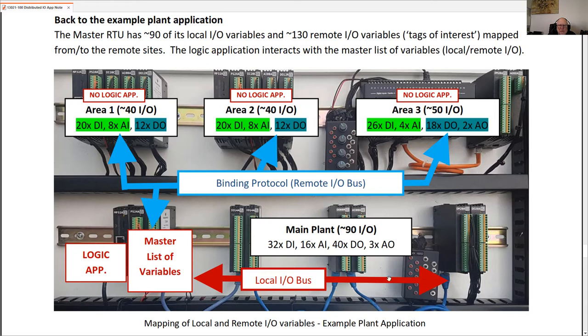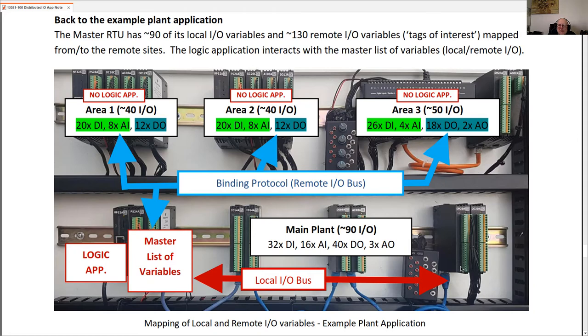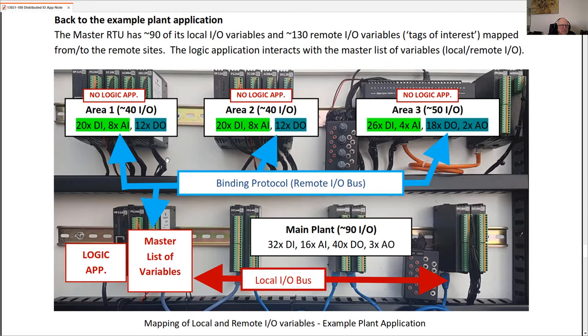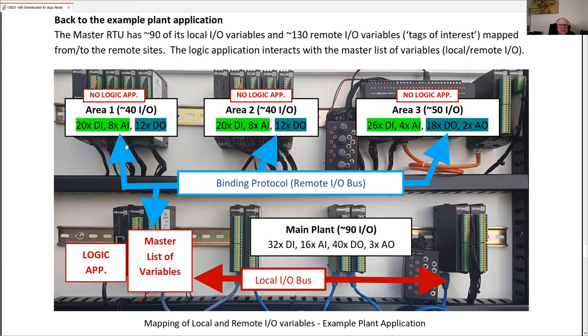The simulator at the end. Cat6 cables passing data and power along those cables. We can monitor the power supply voltage in every module. So we are able to determine that we've got sufficient power resources and watch our data message count to ensure we're appropriately shielded and avoiding interference. And up here we have our remote I/O devices on ethernet connections. And make the point here, no logic applications. So all of the logic is running in the central RTU and it has the master list of variables that allows the logic application to read and write to this list of variables. And magically in the background the binding protocol is how we have mapped these remote inputs and outputs to this master list.